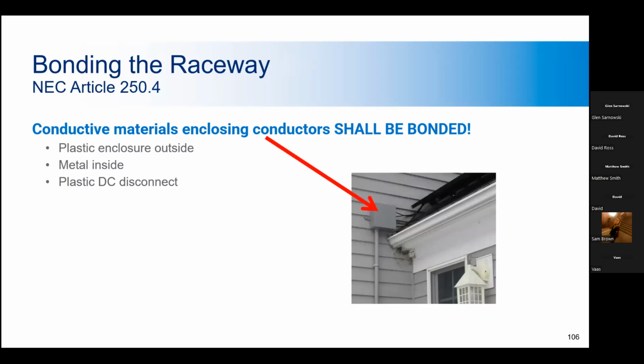We saw an example of this earlier. This is metal conduit going between two non-metallic enclosures. In this case, you would need to see the conduits each bonded and grounded to maintain grounding throughout the system. And you do this through a grounding bushing installed in that panel.